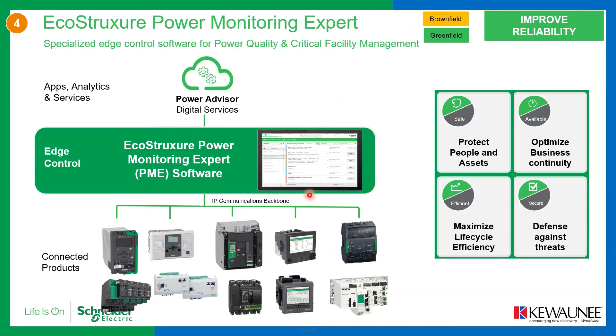One example I just pulled here, for an interesting view, is the power quality performance. If you see the graph, I'll zoom in here. You can see the voltage fluctuation is 100%. Typically the voltage is 415 normally for a three phase. When the voltage exceeds maybe 500 volts, which can come up anytime in the three phase in the transformers, or if it's 11 kV, it can go to maybe 12 kV or 13 kV sometimes. But if this event happens on a time scale of microseconds or nanoseconds, it's fine. There is no major risk of business discontinuity, and it doesn't create any irreversible damage to the equipment.